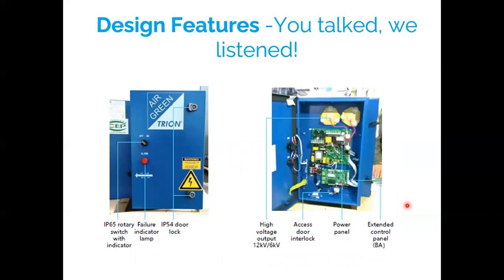So just looking at this one now, what changes have we made to the actual design features of the units? You talk, we listen, because we've spoken to a lot of customers about how we can improve the unit itself. Looking at the door specifically, we've upgraded the switch, so it's IP65 rated now. It's much more robust than the old switch. The failure indicator lamp is for the BMS side, but it also gives you an indication of whether your unit's working correctly or not.